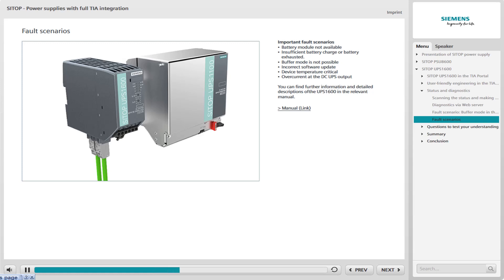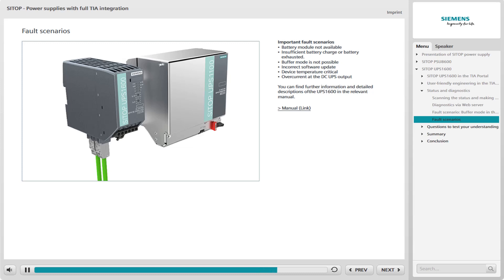Incorrect software update. In this case, the update file is incorrect, damaged or obsolete. Device temperature critical. This message is displayed if temperatures inside the device reach the limit range, because the device could exit the permissible operating range. In this case, the output current of the UPS 1600 is too high. The output is switched off for 20 seconds and switched on again. You can find other fault scenarios, as well as detailed information and detailed product descriptions of the UPS 1600 in the relevant manual.